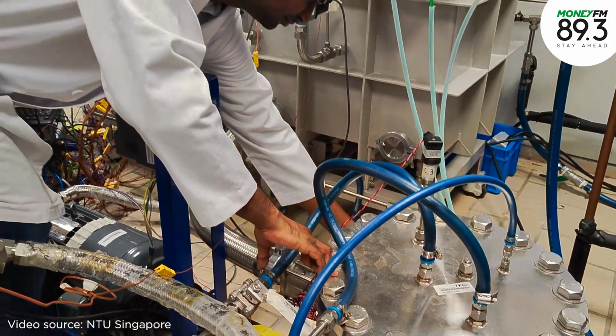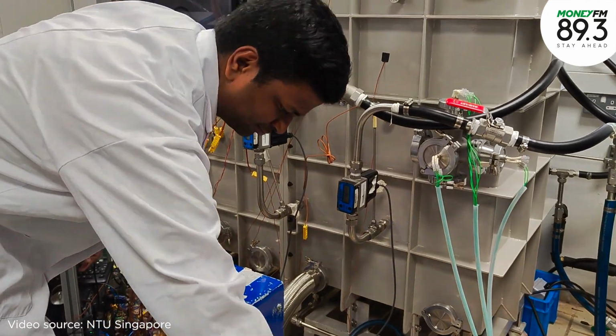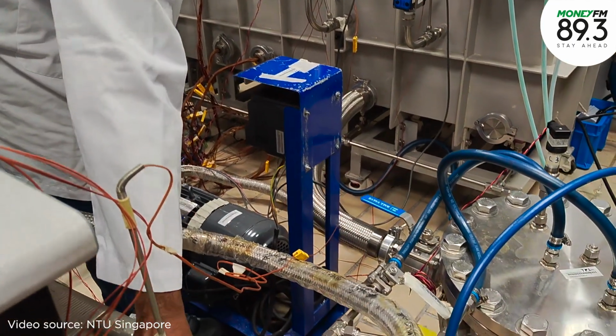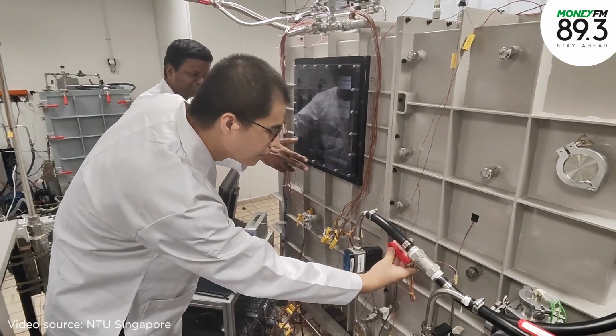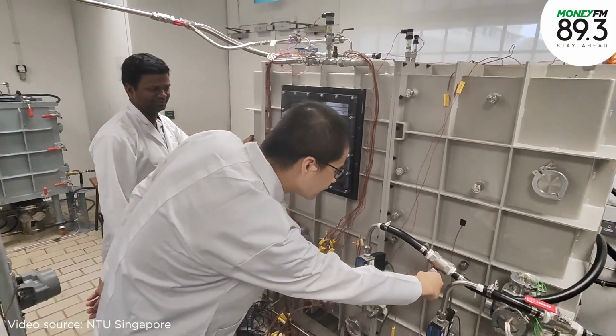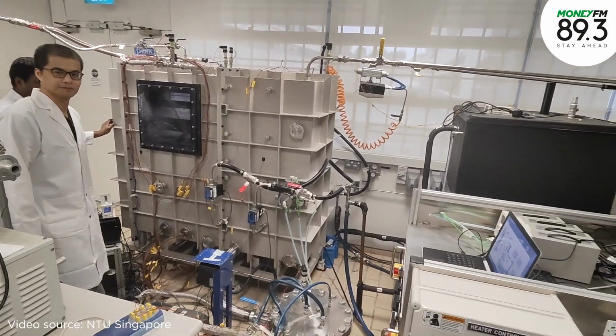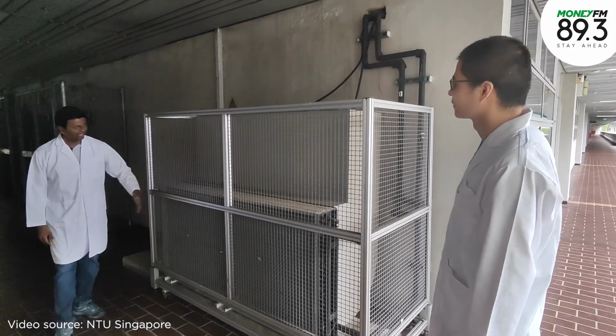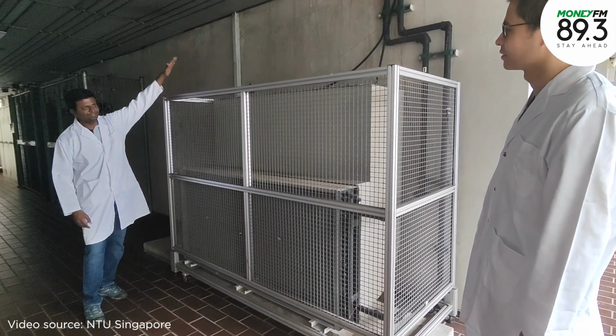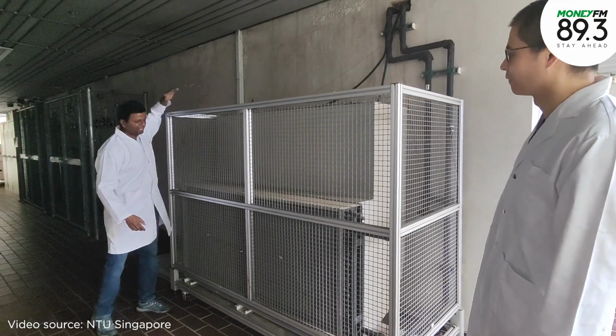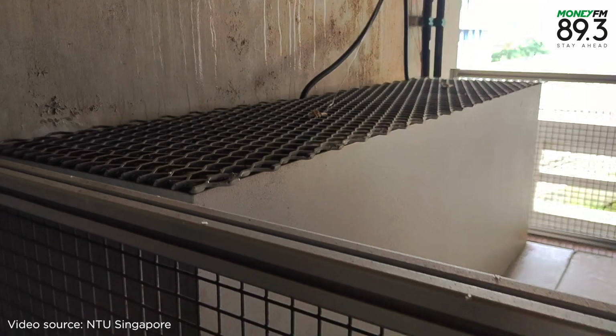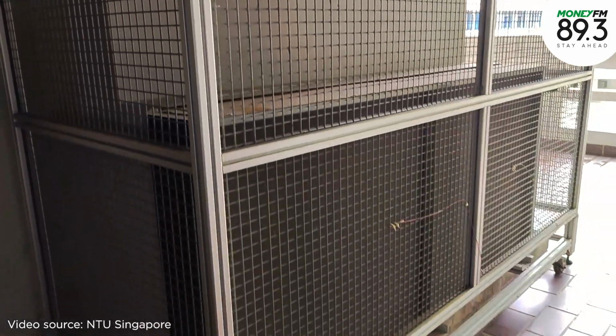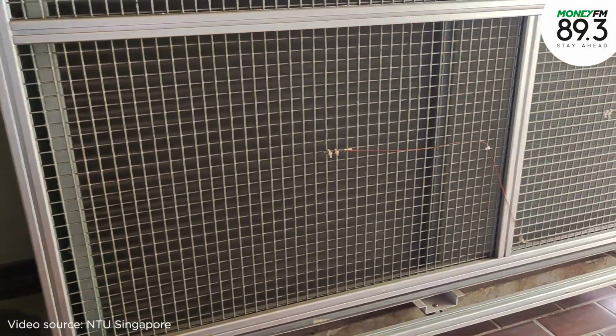How minute are these droplets, and how do you actually supply that infusion of cooling droplets? What we have done is pump the non-conductive liquid through a nozzle, and the nozzle will atomize the liquid into fine droplets. These fine droplets travel at slightly higher velocity and impinge directly on the hot surface. So on the surface itself, there will be evaporation, boiling, and droplet impingement, which can remove heat enormously from the heated surface, like the CPU. By doing that, we do not need a conventional heat sink attached to the CPU to draw heat away, so we have removed the heat sink and performed that part of the cooling function.